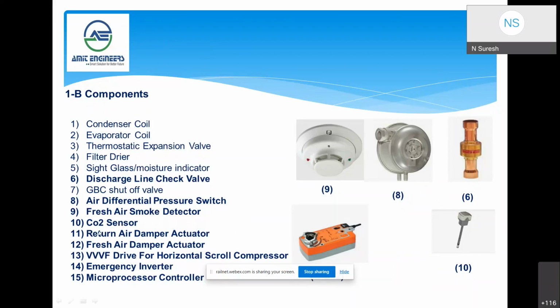of view. There is a CO2 sensor. This is a CO2 sensor to maintain the ppm level inside the coach. Return air damper actuator. This is how it looks. This is an automatic retainer damper actuator connected to the microprocessor controller. And there is one fresh air damper actuator. A triple VF drive for the horizontal scroll compressor, as I briefed you earlier, and there is one emergency inverter and microprocessor controller, one controller for 2 units.